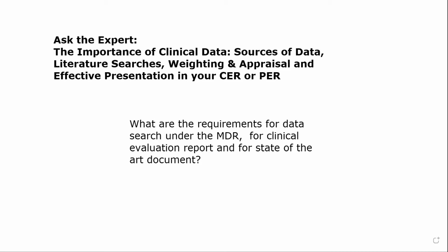That state-of-the-art search is using PICO terms. It's looking for guidelines, professional standards. It's not data-driven. It's the telling-the-story search, the one that I just described. So that's search number 1. It can be handled differently because it does not include data, and it doesn't need to be documented as rigorously in the CER or any of your documentation as the next 2 that I'm going to talk about.